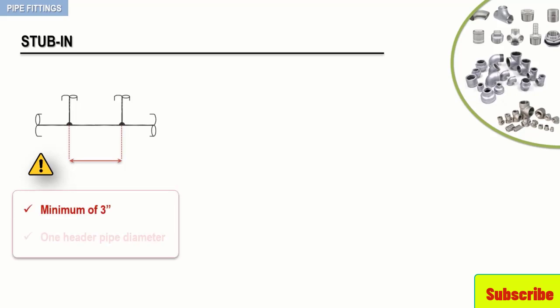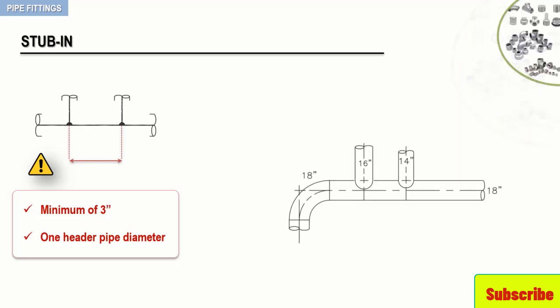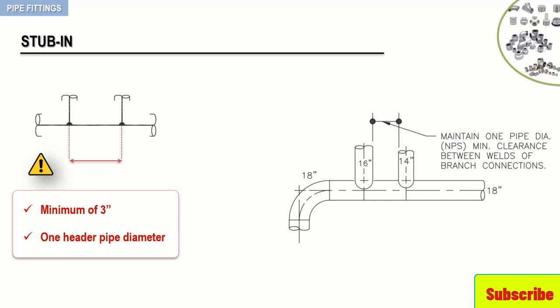To better illustrate this concept, let's have a look at the following piping configuration. Here we have two stub-ins — 16-inch and 14-inch — on an 18-inch pipe. According to best welding practice, we should maintain one pipe diameter as minimum clearance between the two welds. This means 18 inches is the minimum spacing between the two branches when attached to a common header.